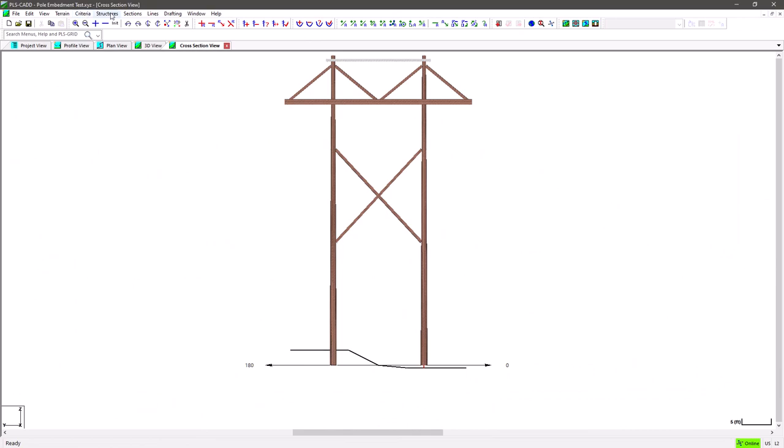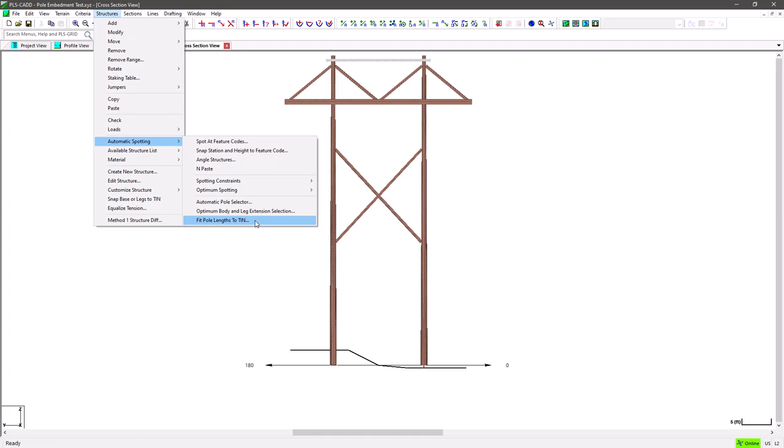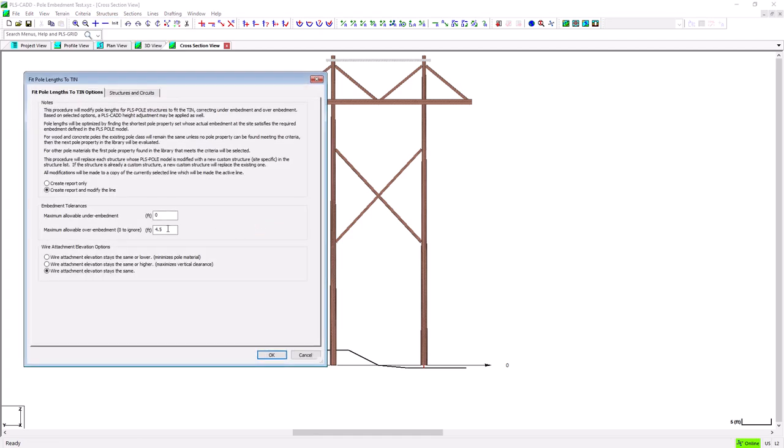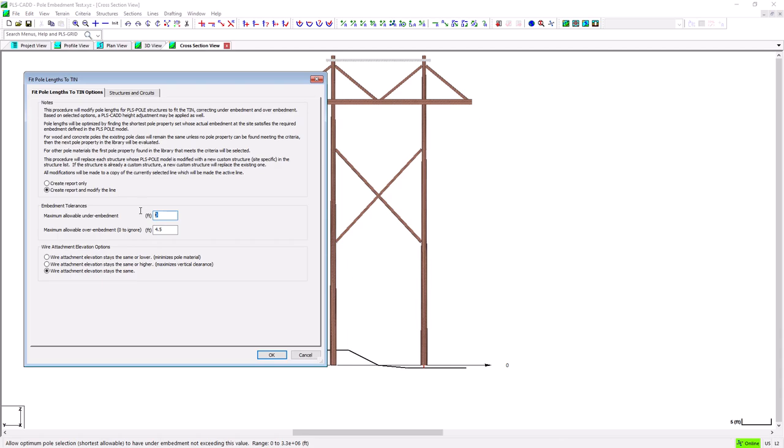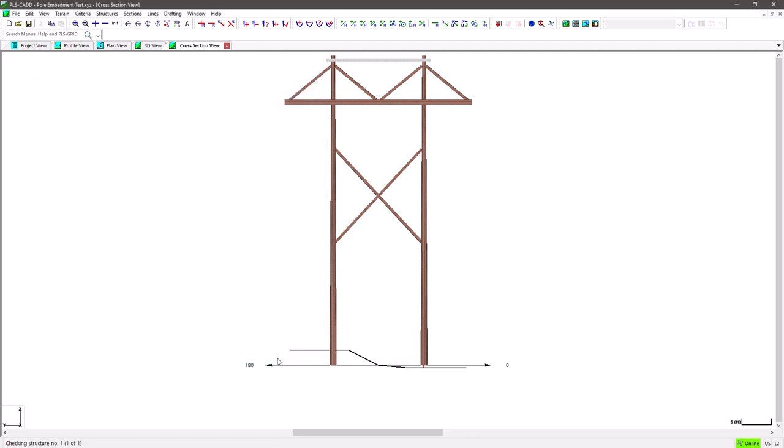Or if you're looking at the Leg and Guy Extension Report, you want the additional length to intersect the tin to be 0. So let's start by using this feature and saying that an over embedment of 4.5 feet is acceptable, and we don't want to allow any under embedment, so we'll leave that set to 0. We'll also keep things simple for now and choose the setting to make sure the wire attachment elevations stay right where they are and that the program will know that making a structure height adjustment isn't allowed. And we'll also check the option to go ahead and modify the structure so we can graphically see what it looks like when we run the report.